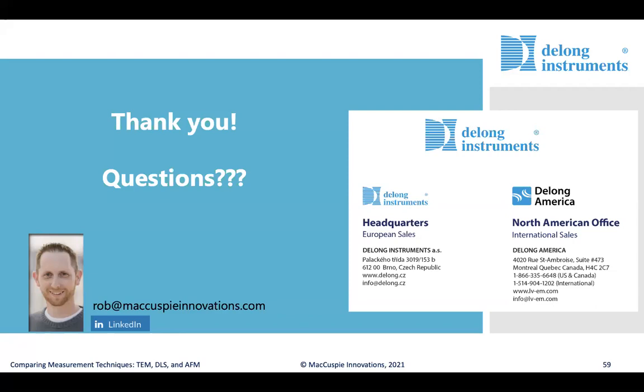To add a finer point on DLS size distributions: studies in the peer-reviewed literature have shown that if you have a multimodal size distribution, you need at least a factor of two to three difference in the diameters to resolve the different peaks well by DLS. If the two peaks are close to each other, the software can produce overlapping results and you'll see what looks like a broad single-sized distribution instead of a finite multimodal distribution. It's definitely something to pay attention to when interpreting DLS measurements.